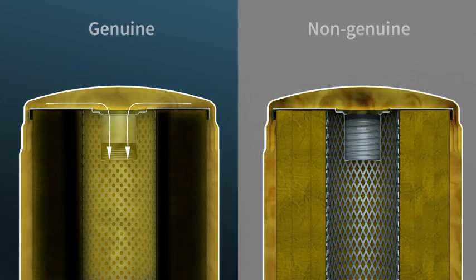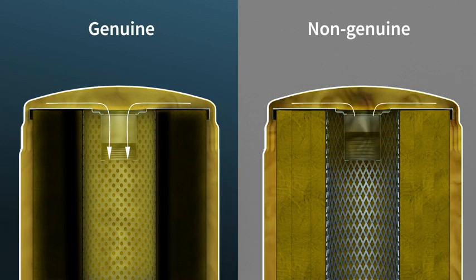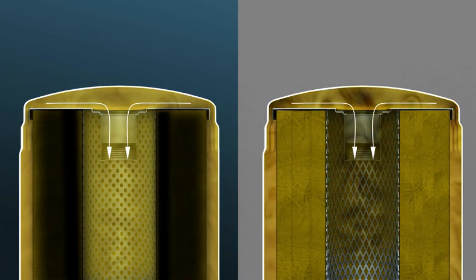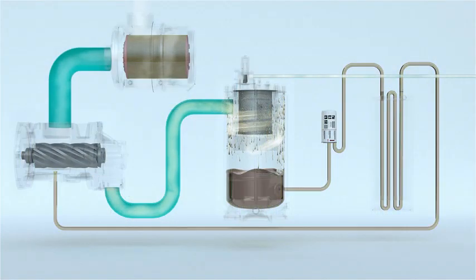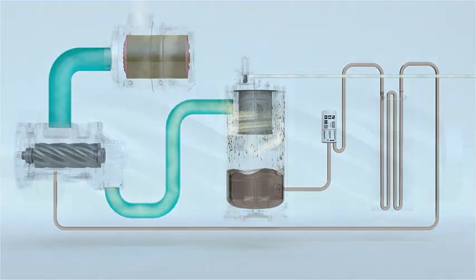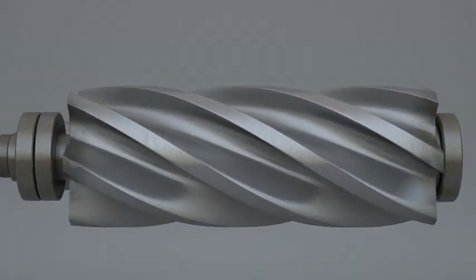If the bypass valve is too weak, it will open too easily, letting unfiltered oil flow freely into the system. This unfiltered oil will end up all over the oil circuit, damaging different components like bearings, coolers, and the compressor element.